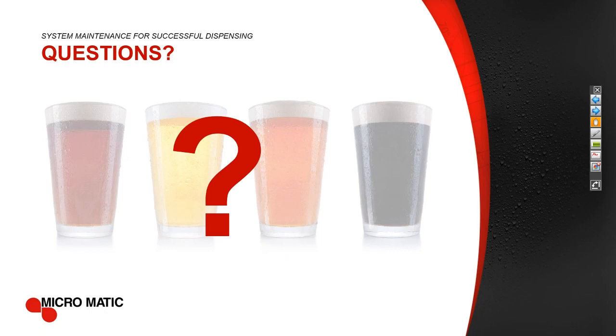And when we are using the static or soaking cleaning, that is certainly something that can happen if we leave the water in for an extended period of time. But as long as that water and chemical are moving through the system, think about a river. If you're in a cold area, even though it's frozen on top or on the sides, it's moving underneath, right? So personally, when I first started, I turned a power pack off and it didn't turn back on. So I just got kind of burned, and it's pretty much my rule of thumb that I leave them on.